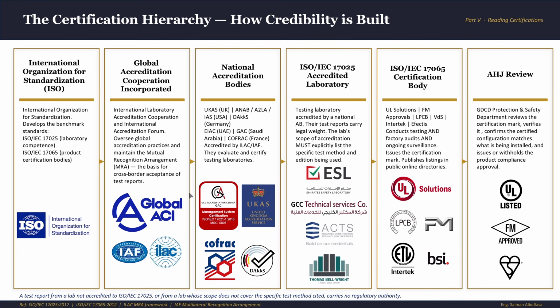Now the laboratories that physically conduct the fire tests and issue the test reports. Their accreditation is ISO/IEC 17025. So when we say an accredited lab or an approved lab, that means the lab has this accreditation, 17025. But the accreditation is not general and not for everything. It has specific authorization by test method, by edition, by product category. So it's not one certificate to test everything you can do. And they do get a calibration check, for example.